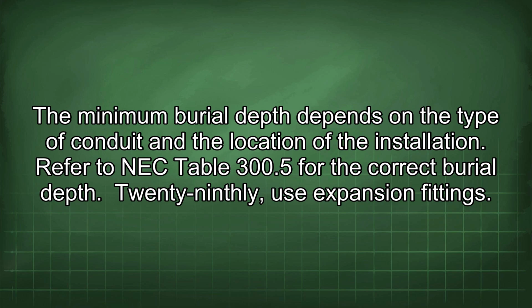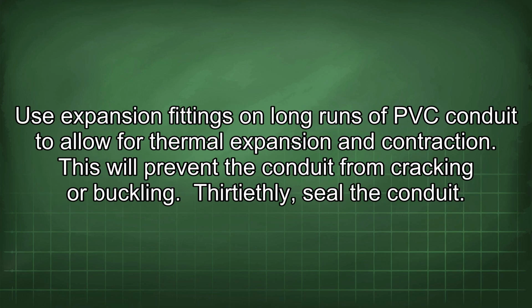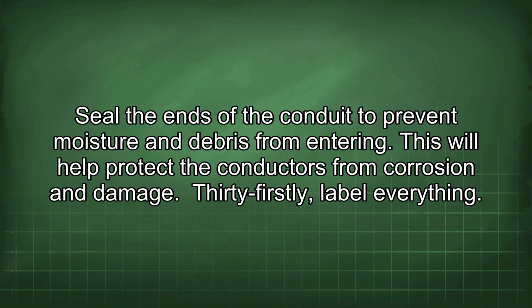29thly, use expansion fittings. Use expansion fittings on long runs of PVC conduit to allow for thermal expansion and contraction. This will prevent the conduit from cracking or buckling. 30thly, seal the conduit. Seal the ends of the conduit to prevent moisture and debris from entering. This will help protect the conductors from corrosion and damage.